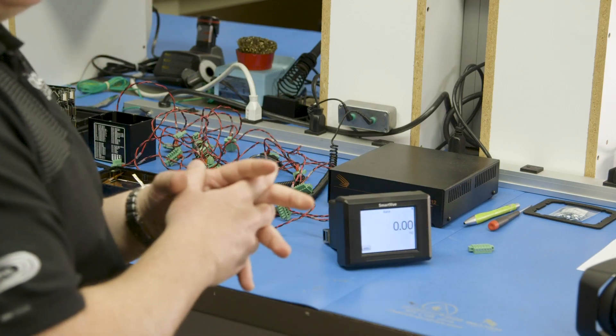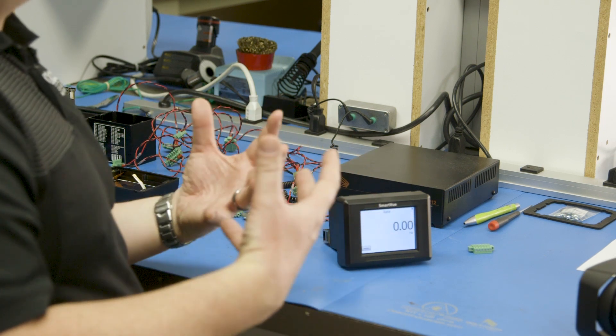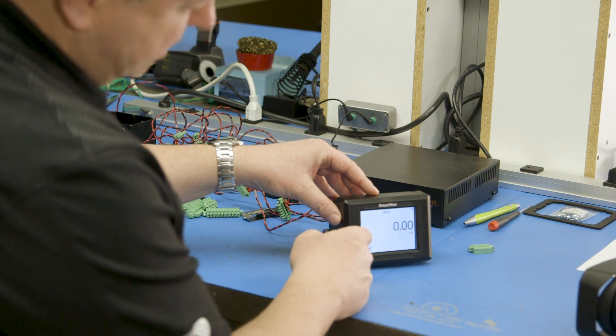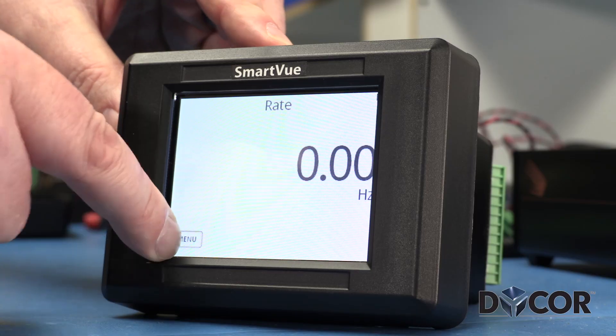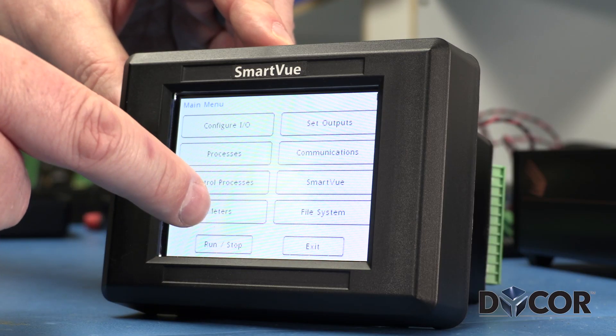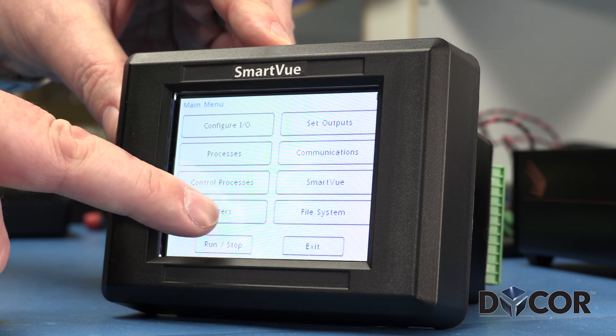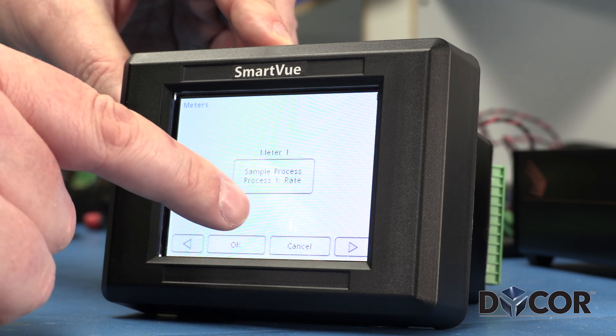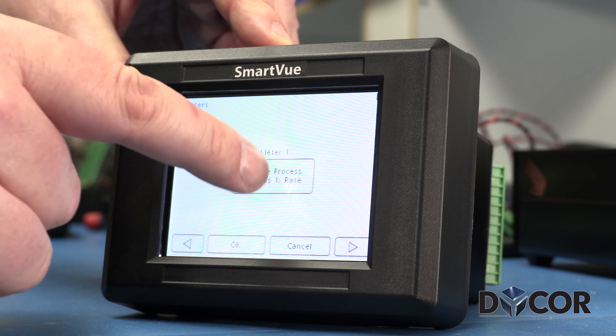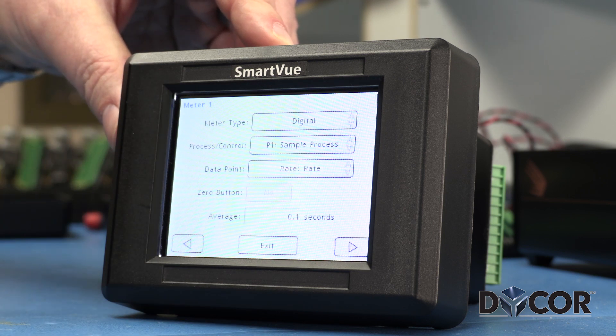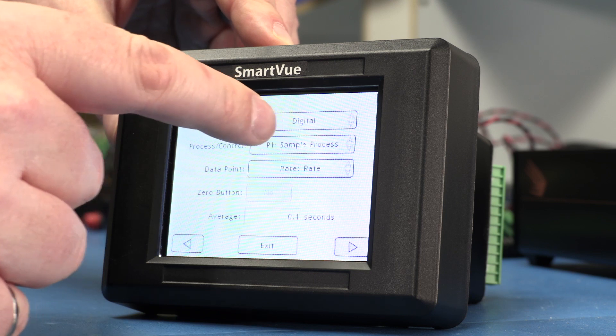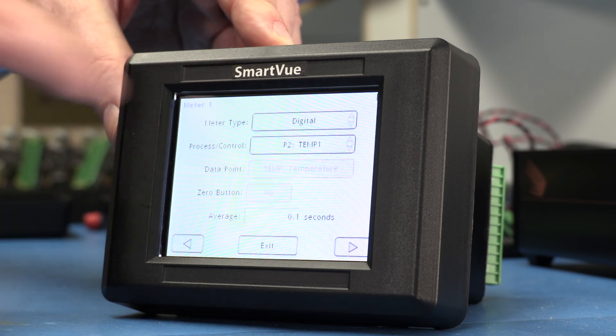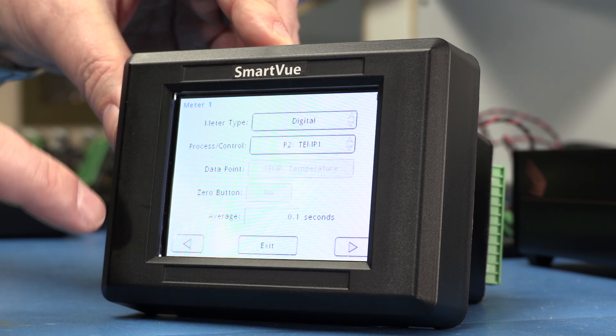I'm still showing Process 1 on the meter screen. So now I want to display a meter for that new temperature process — I'm going to replace this rate counter process with the temperature process I just created. I'll do that by pressing the meters button on the main menu and change Meter 1 from the existing default process to the P2 Temp 1 process I just created.